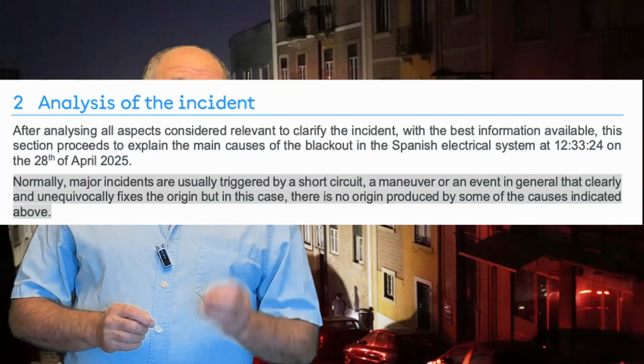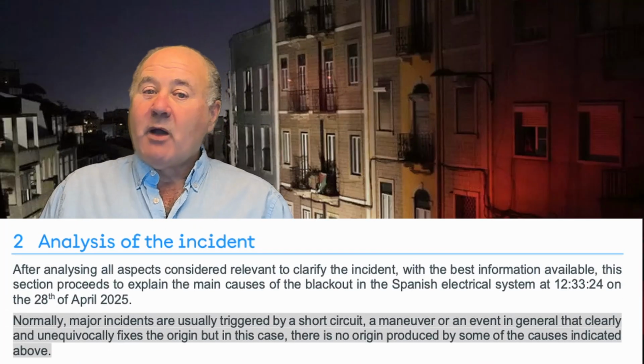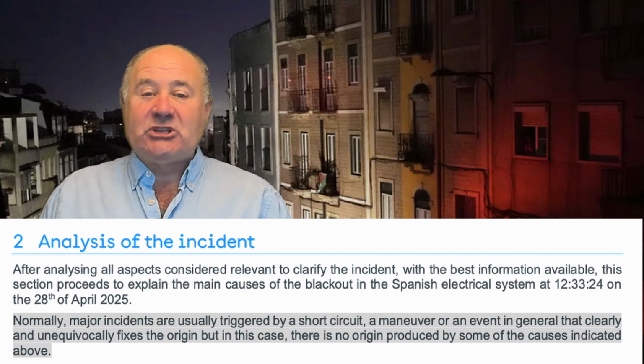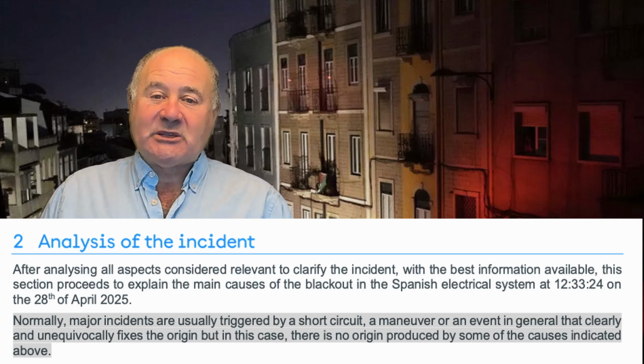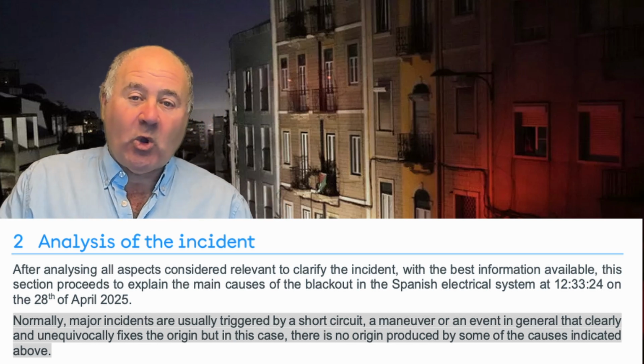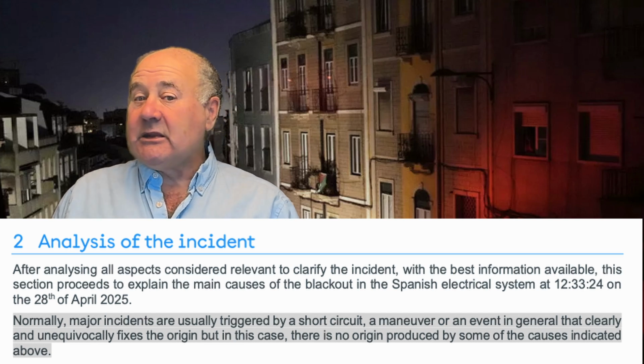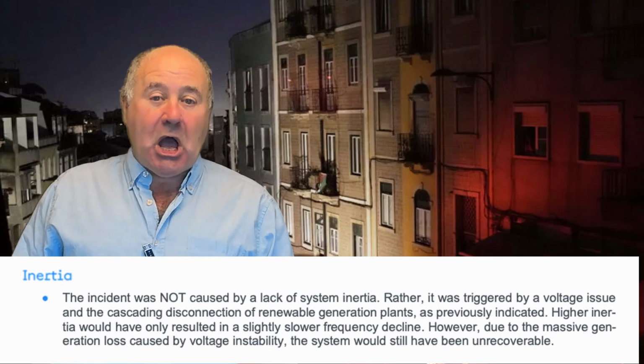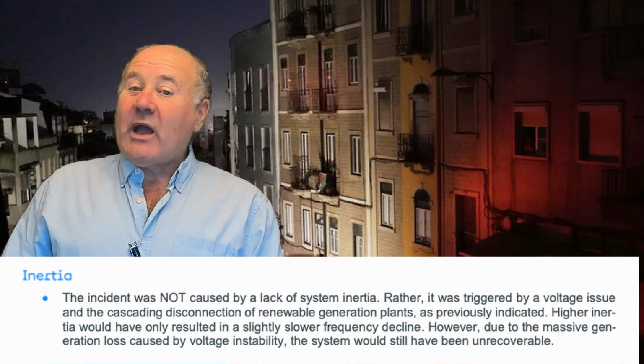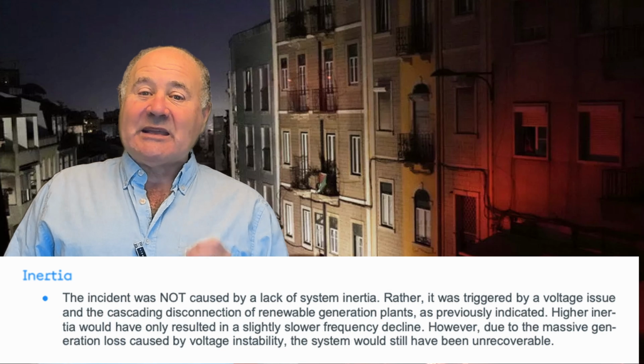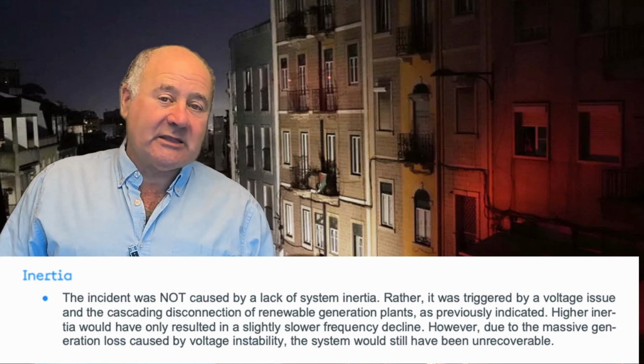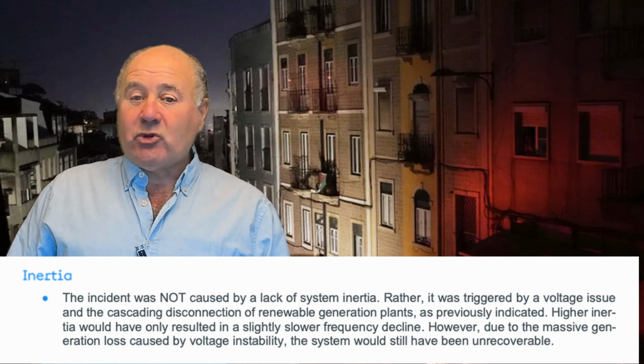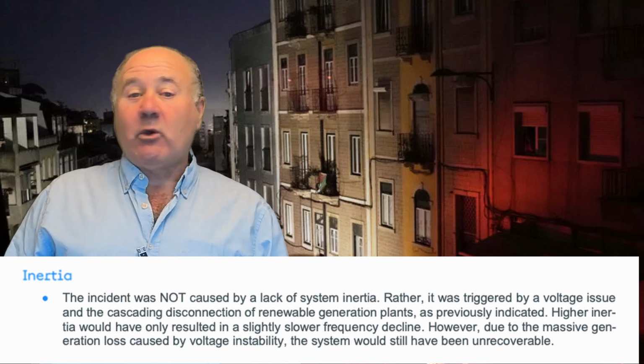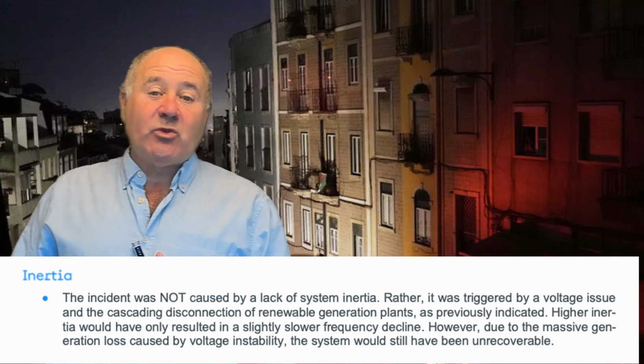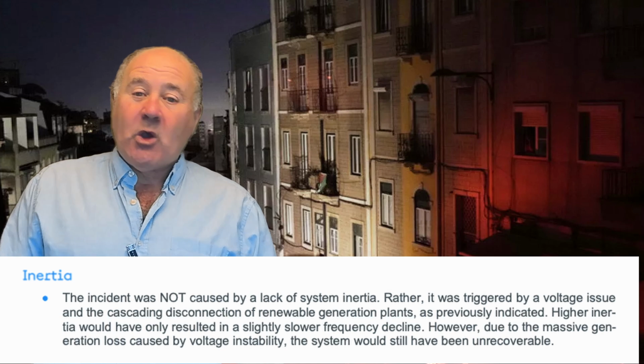Early in the report, they say normally major incidences are usually triggered by a short circuit, a maneuver, or an event in general that clearly and unequivocally fixes the origin. But in this case, there is no origin produced by some of the causes indicated above. The incident was not caused by a lack of system inertia. Rather, it was triggered by a voltage issue and the cascading disconnection of renewable generation plants, as previously indicated. Higher inertia would have only resulted in a slightly slower frequency decline. So those who thought that the problem was renewable resources without spinning turbines providing inertia were wrong.